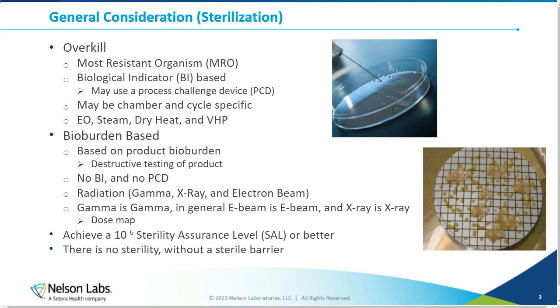So anytime you're making a change, that's going to be something that needs to be considered. Some examples of overkill methods are your EO, steam, dry heat, and your vaporized hydrogen peroxide. The other sterilization modality is going to be your bioburden based. That is going to be based on the bioburden of the product. There's not a most resistant organism. There's not a biological indicator. It's the actual bioburden on or in your product. And since it is based on the product's bioburden, we are going to be testing that product. Generally speaking, that's going to be a destructive test so that we can find that bioburden. So again, there's no biological indicator, there's no PCD, we're testing directly to the product.